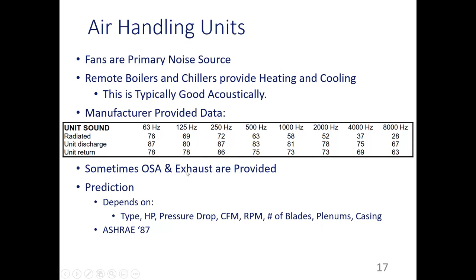Like I said, sometimes outside air and exhaust are provided. I was talking about how those manufacturers' data sheets will have the bare fan sound power level, and ideally, what is more important, they have the supply and the return, and then they have outside air and exhaust if needed.